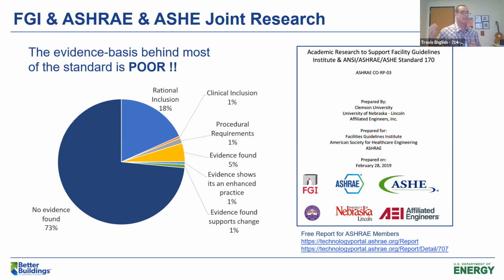I'll come back to this at the end. A lot of people have beliefs about air and health, much of which is fear, myth, superstition, tradition, folklore, whatever you want to call it. Sadly, healthcare ventilation is one of the most non-scientific aspects of building engineering. We have about 5 rooms in hospitals where air quality and movement are really clinically important, but then our standard has an air change table with literally 100 spaces, all these non-evidence-based prescriptions of 4 air changes per hour, 6 air changes per hour, all over the place. Those numbers are really meaningless in terms of evidence - you might as well hang garlic around the building to ward off vampires.